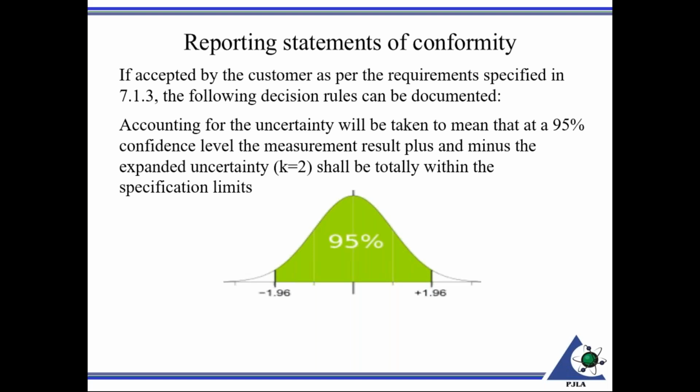Before we revised P11 3, which is our policy on measurement uncertainty, we gave a little bit more guidance on that. We coined the phrase, not making this a requirement, but instead of saying pass, pass indeterminate, for when uncertainty actually may affect it, or fail indeterminate. When I was on the calibration side of the table, I used to put a little asterisk next to those points and then define at the bottom what that meant.